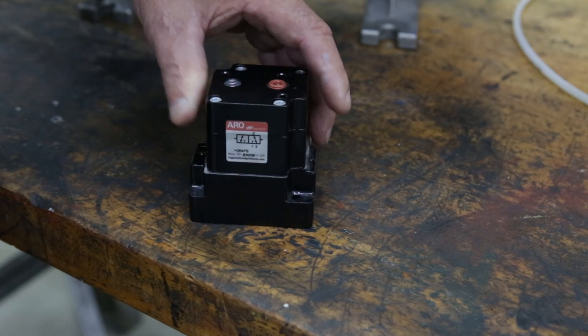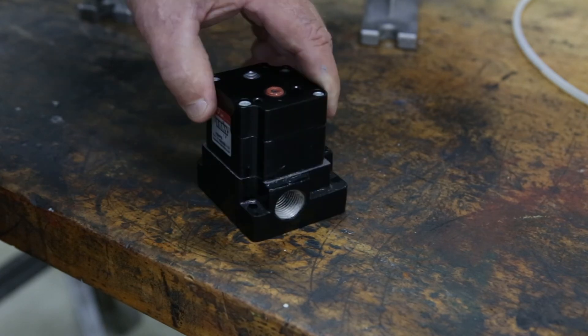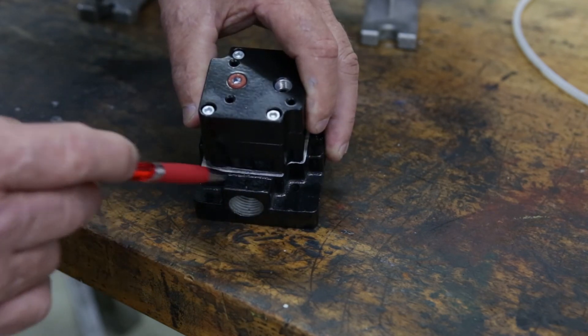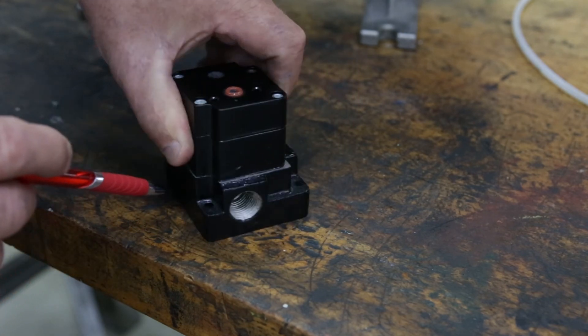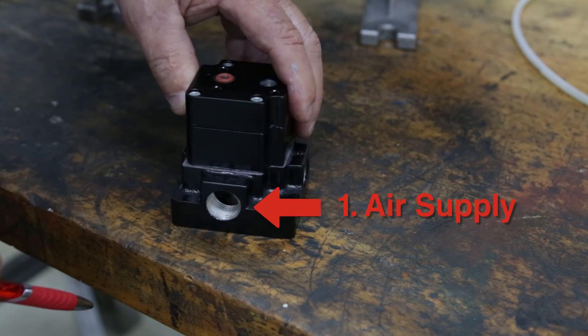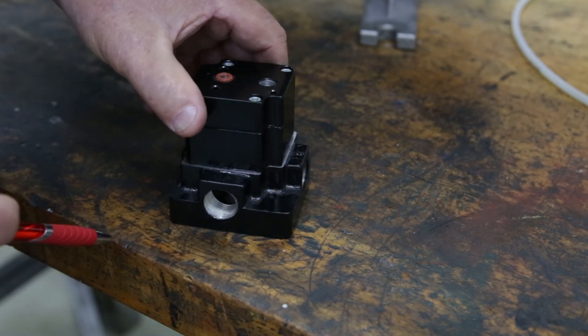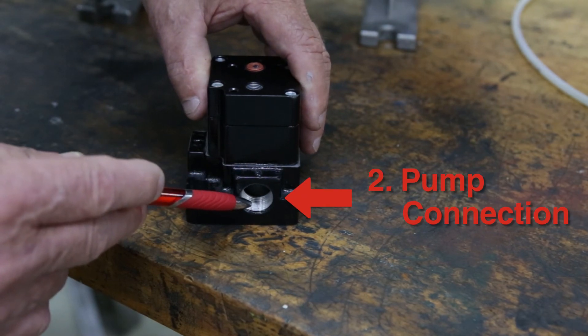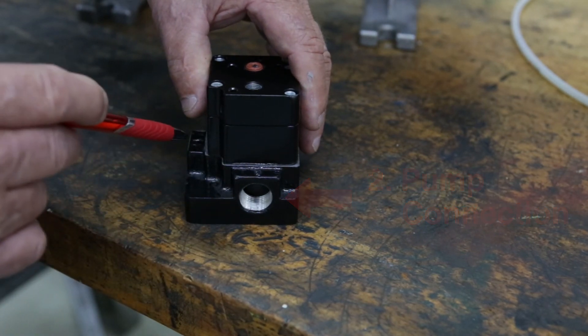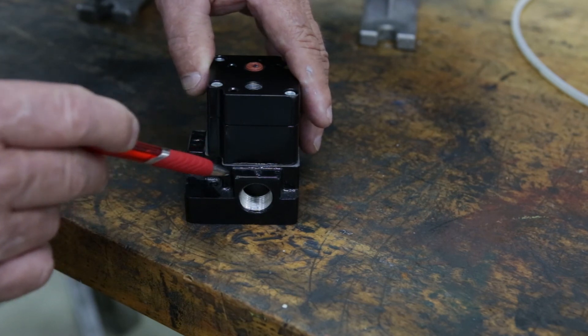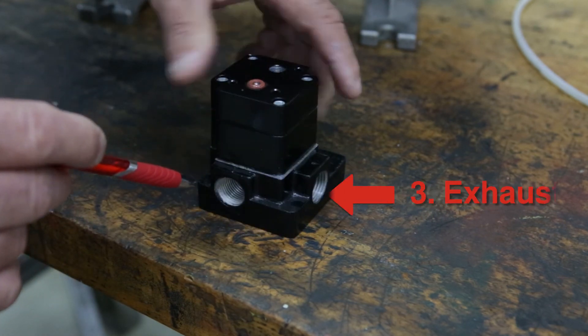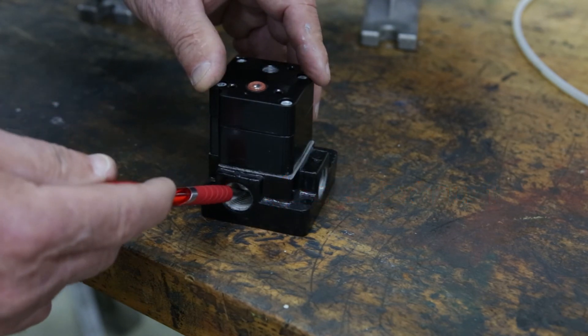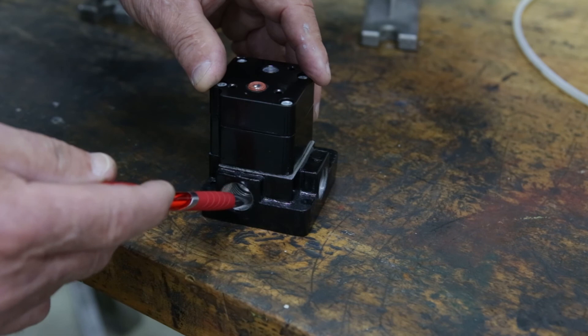This is an H-series ARO valve. It's a pilot-operated, normally closed, three-way valve. You'll notice on the body itself, there are numbers corresponding to each port. Port one is always air supply. Port two is connected to the pump itself, so when the valve is on, air will flow from port one to port two. And port three is exhaust. When this valve is turned off, we're going to exhaust all the air from the motor and the pilot through this port.